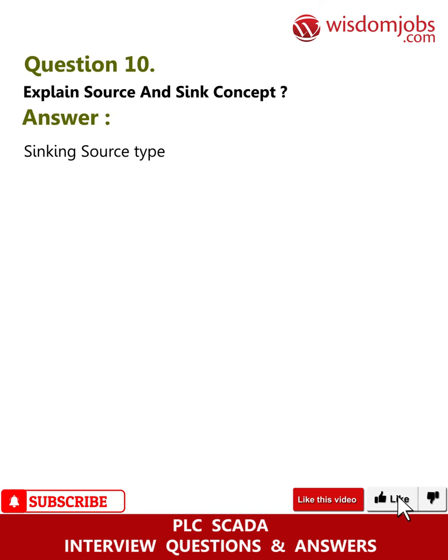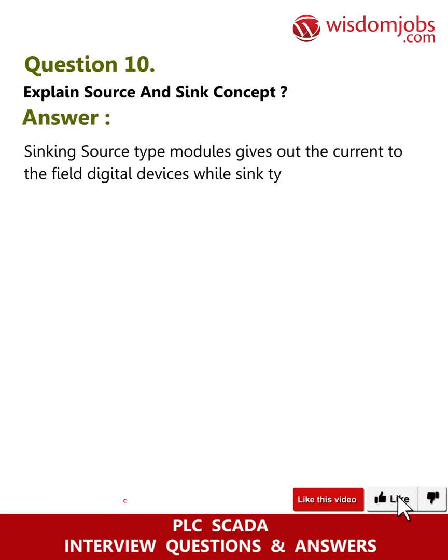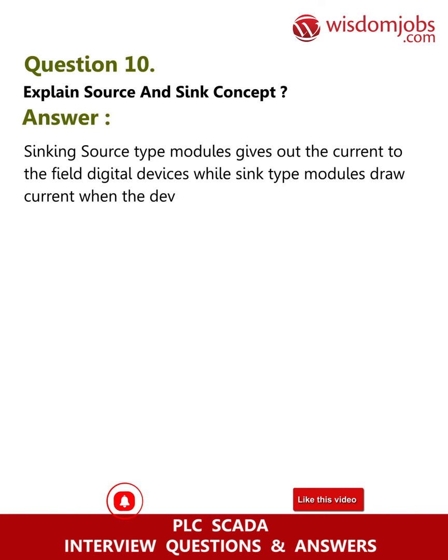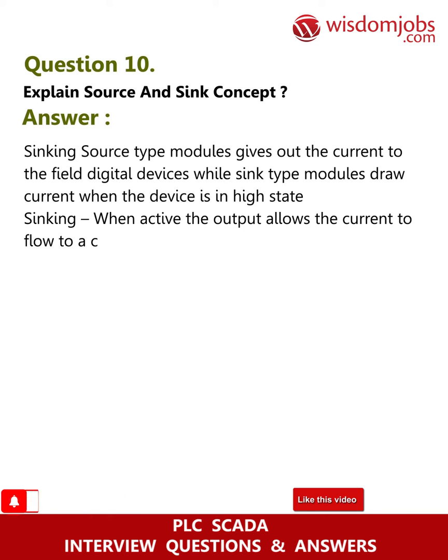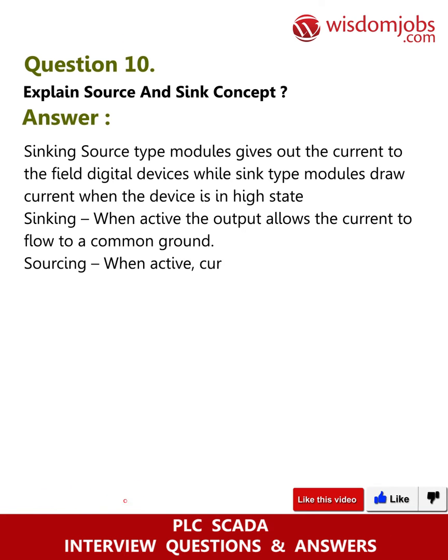Question 10: Explain the source and sink concept. Answer: Sourcing type modules give out current to the field digital devices, while sink type modules draw current when the device is in a high state. Sinking: when active, the output allows current to flow to a common ground. Sourcing: when active, current flows from a supply through the output device and to ground.